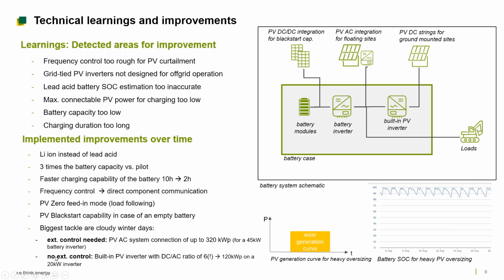Second option, excluding any control, so quite robust, is the built-in PV inverter that we chose, because here we can realize a DC-AC ratio of 6. That means we can put 120 kilowatt peak of PV power on a 20 kilowatt inverter.